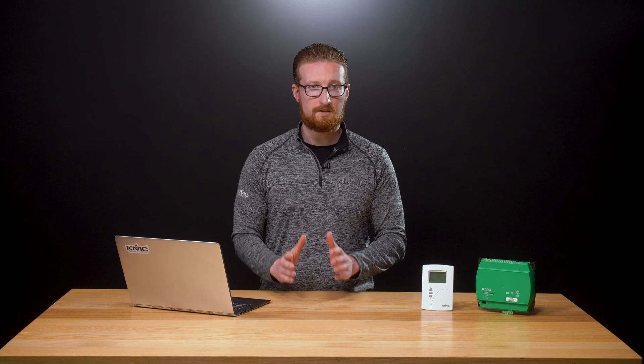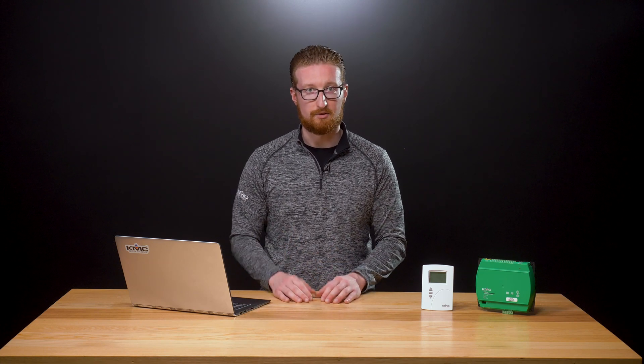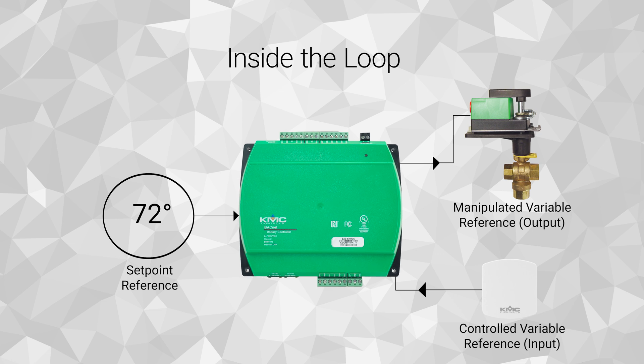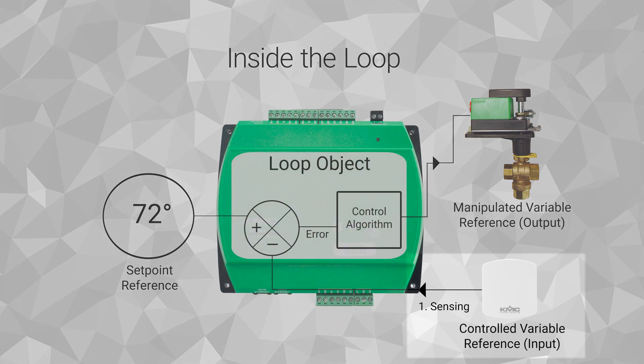Now that we know what pieces are involved in our control loop, let's break down the four-step process running inside the control loop. The loop maintains control of either a flow, pressure, or temperature by the following. First, by sensing a condition such as a zone temperature, air flow, or duct pressure by using the appropriate sensor for the process.